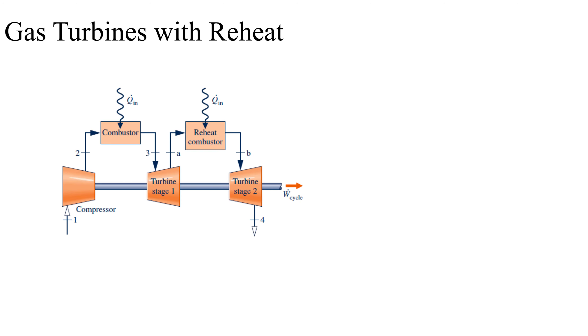Looking at the schematic, the change you would notice is that instead of a single-stage turbine we've got a two-stage turbine, and instead of a single combustion chamber we've got a reheat combustion chamber as well. That means we are adding heat content twice instead of just once as we did previously.